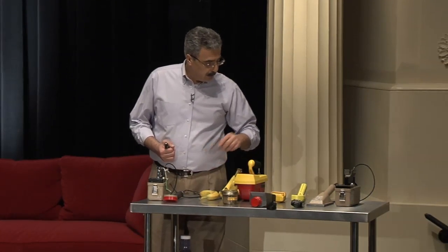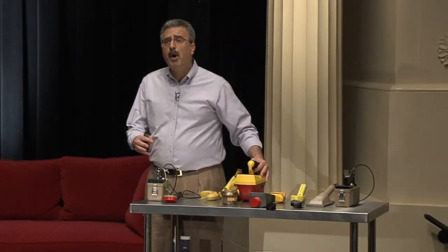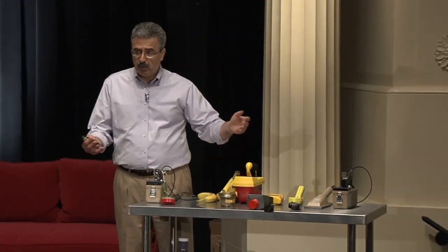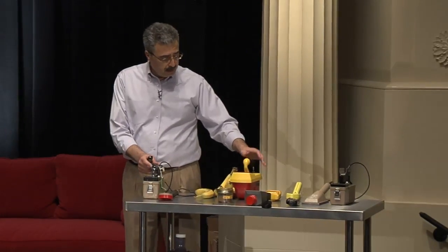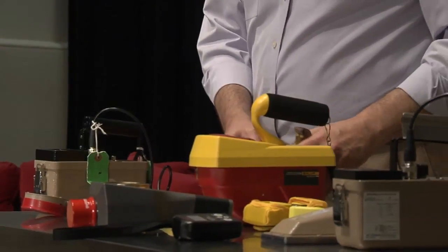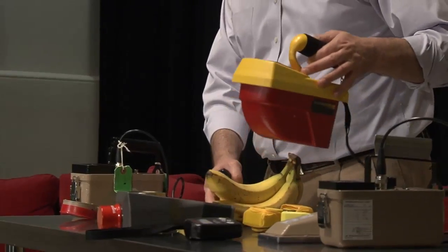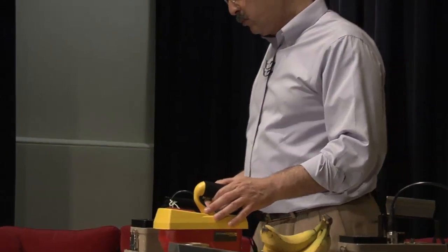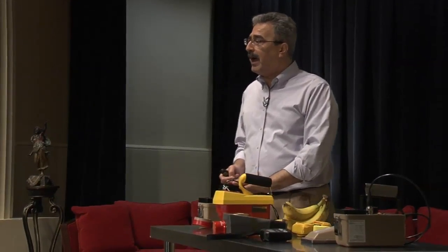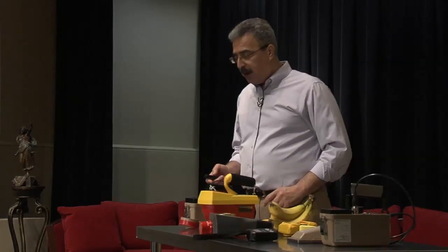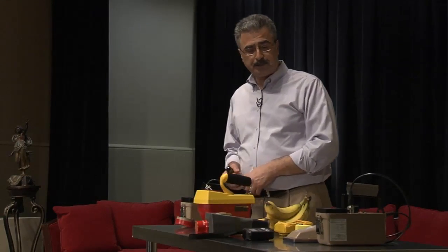Another instrument is the ionization chamber, and there are different models of this. The ones I have here are just one particular model, but there are different brands and models of all of these instruments. The ionization chamber is a very good instrument to measure ambient radiation levels. Geiger counters would give us an idea about whether the ambient radiation levels are high or low, and give us some measure. But to make a more accurate measurement, we would need to use an ionization chamber.